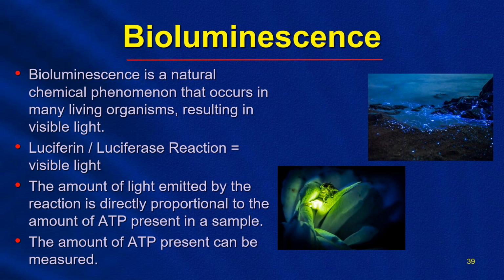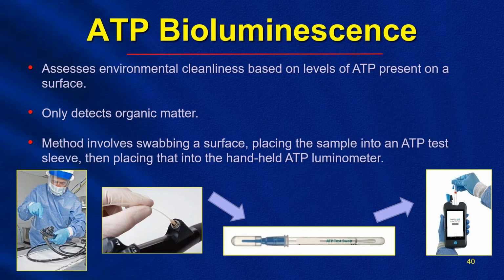So the presence of ATP on medical devices, instruments, or surfaces may be an indicator of residual contamination. Modern bioluminescence tests are based on the reaction of luciferase extracted from fireflies with its substrate luciferin, known as a luciferin-luciferase reaction, which generates light. Now, the amount of light emitted in this reaction is directly proportional to the amount of ATP present in the sample. The ATP bioluminescence testing for cleanliness is based on the measurement, again, of levels of ATP. It will detect organic matter, but will not be able to detect pathogens that cannot produce ATP, such as viruses.